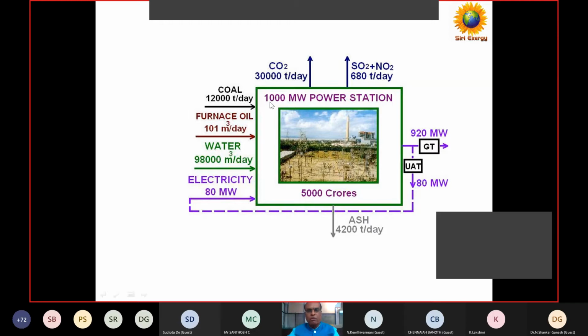So whatever you are generating, say 1000 megawatt, then there is 80 megawatt internally consumed inside the plant for auxiliary power. So only 920 is exported through the GT - not gas turbine, it is generator transformer. This through generator transformer will step up to 220 kV and finally get distributed. So this is the typical setup.